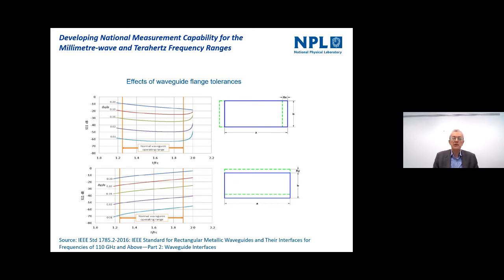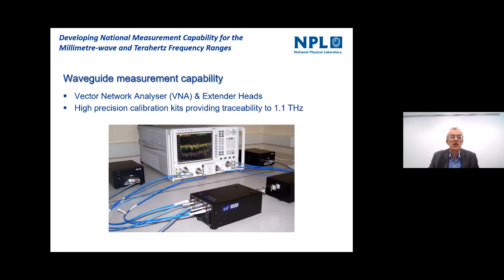So the way we operate is we fully characterize our devices, the test ports that we have on the measuring instruments, the standards that we use and the devices that we might be measuring. We can fully characterize those and then turn that into a measurement capability. So on the next slide here, I show a measurement capability that we've established for this type of work. This is a vector network analyzer, which you can see in the background there. It's a standard unit that you can buy from different manufacturers.